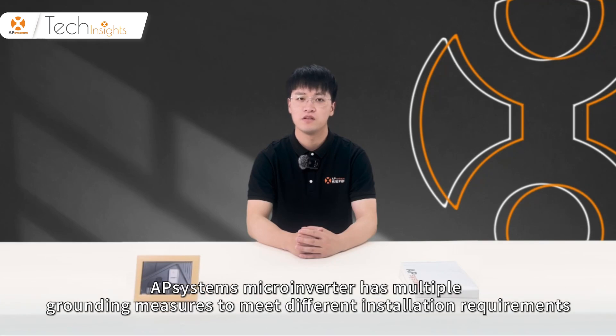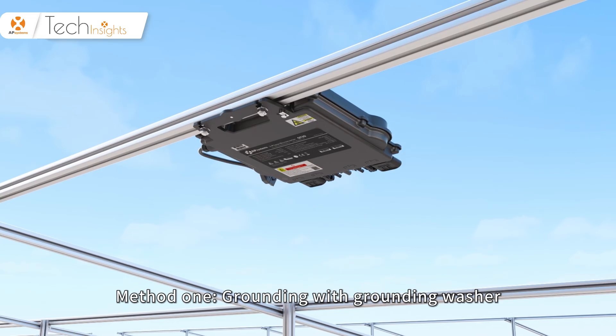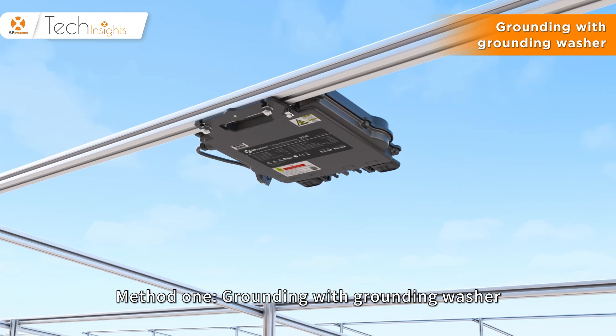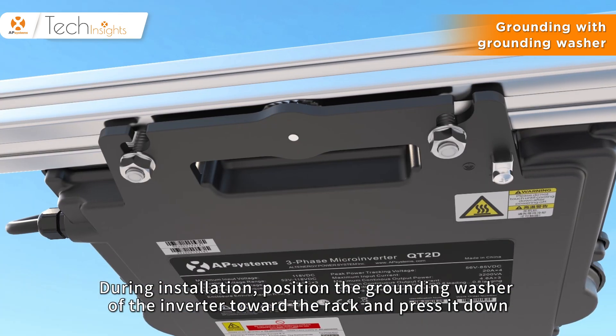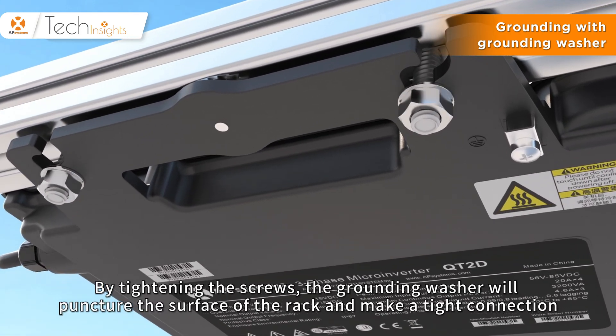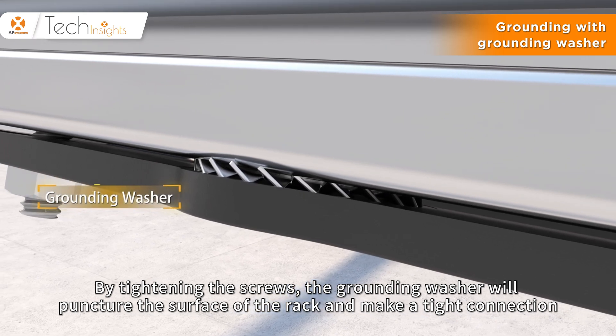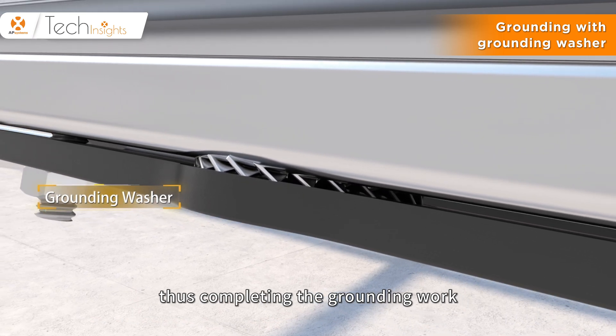An APsystems microinverter has multiple grounding measures to meet different installation requirements, including the following three methods. Method 1: Grounding with grounding washer. During installation, position the grounding washer of the inverter toward the rack and press it down. By tightening the screws, the grounding washer will puncture the surface of the rack and make a tight connection, thus completing the grounding work.